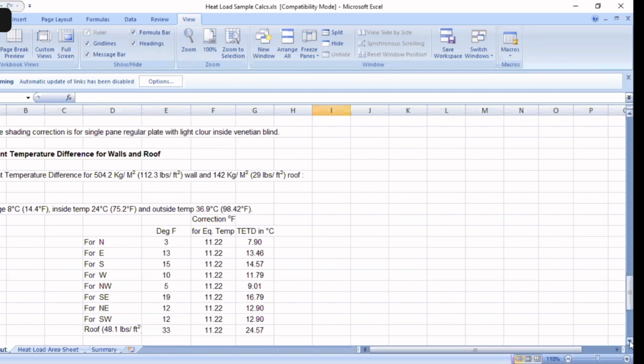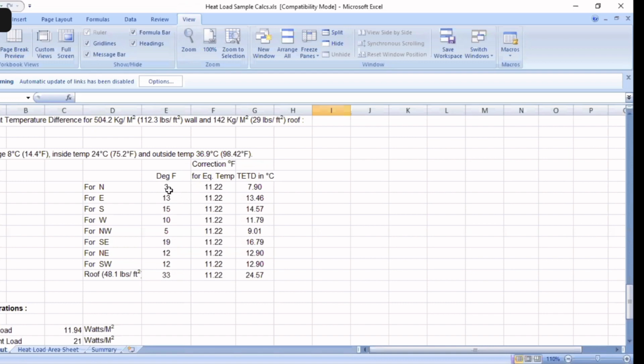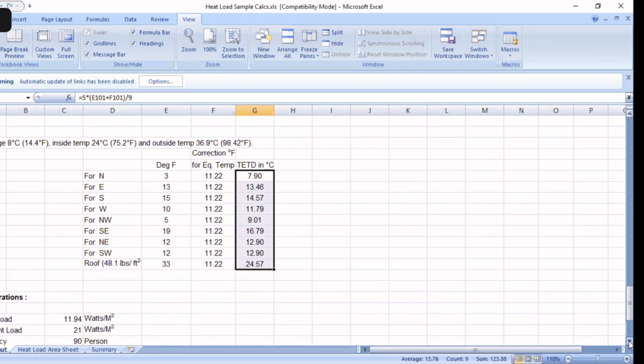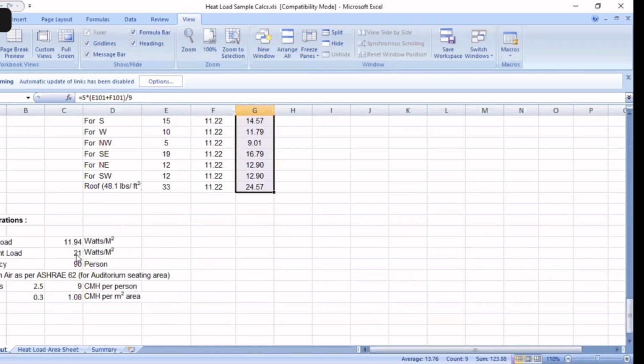So I have again considered the Carrier handbook for north side wall, etc. TETDs are this. Then correction factor. These TETDs were given for a particular temperature inside and outside and particular daily range. So I have corrected it, and considering the correction factor, this will be my final TETD. Lighting load I have considered this, equipment load I have considered this, occupancy for the seminar hall I have considered 90, ventilation rate I have considered 9 CMH per person and 1.08 CMH per meter square area.